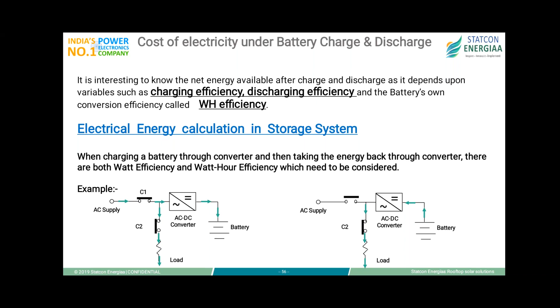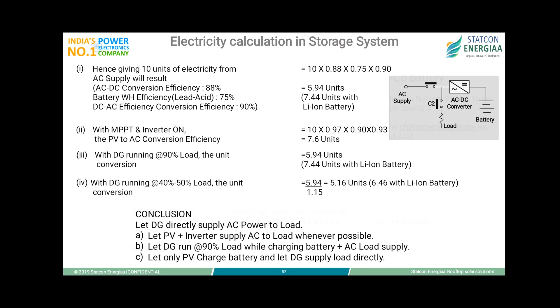These are just some sample calculations—since time is limited, I'll give you the gist. If you are feeding 10 units of energy, and storing it before discharging to the loads, you end up with only 5.94 units—a wastage of more than 4 units, or over 40% of energy. And if this is done through a partially loaded DG set, there's another loss of 15%.